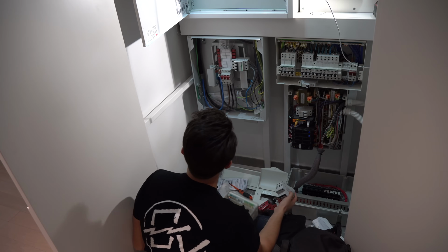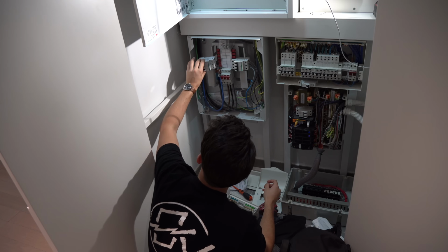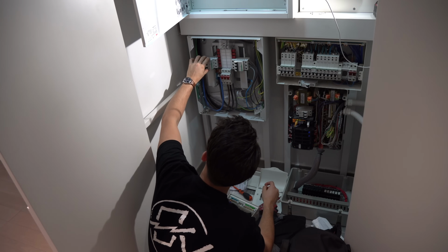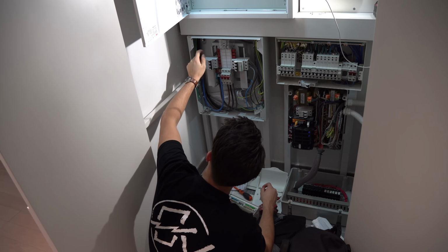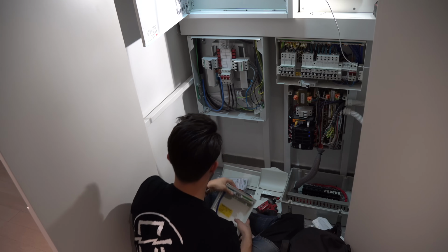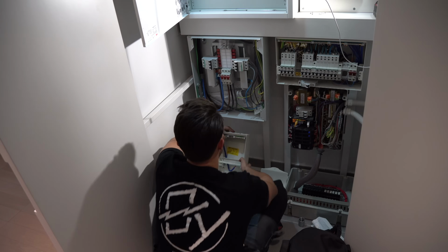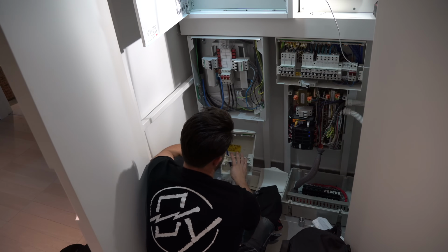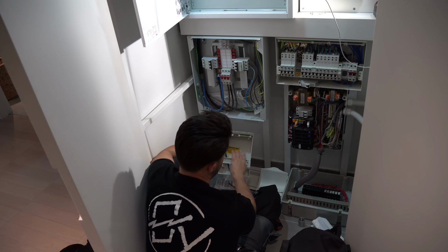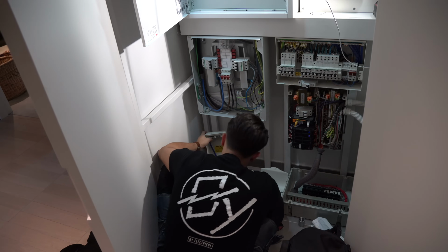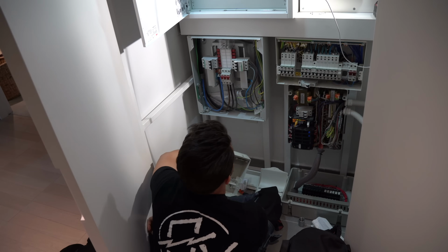So they want to fit surge protection. What I'll do is fit inside this board here, that way around, a 63 amp C curve breaker, three phase. That will come out then to this, where I'm going to have inside of here the actual surge protection. I'm just trying to think how to mount this. There's not really a very sensible place to do it.